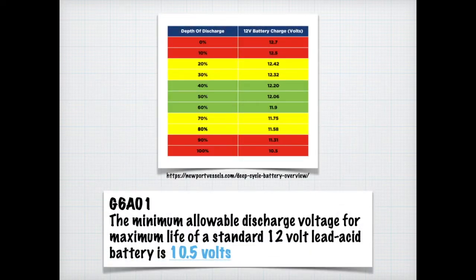If you encounter a question on the test that says, what is the minimum allowable discharge voltage for the maximum life of a standard 12-volt lead-acid battery? If you look at this chart, you can tell that there's a definite red zone. You can overcharge and undercharge a lead-acid battery. For the exam, you just need to know that the minimum allowable discharge voltage for the maximum life of a standard 12-volt lead-acid battery is 10.5 volts. Don't let your batteries get below 10.5 volts. It shortens their life.